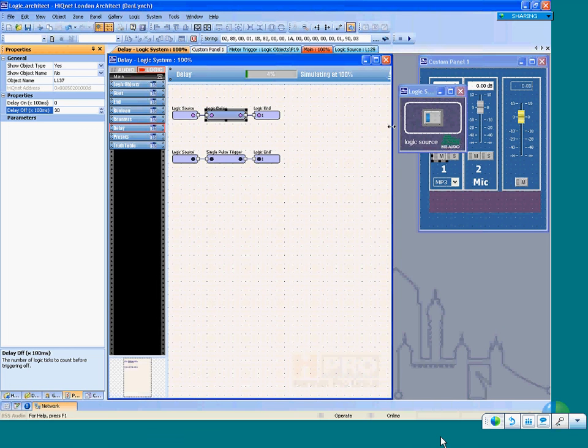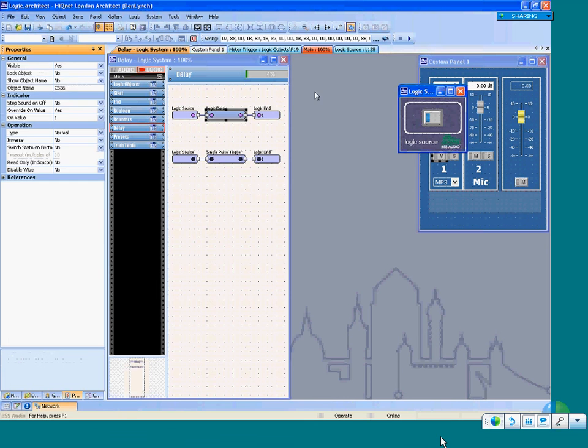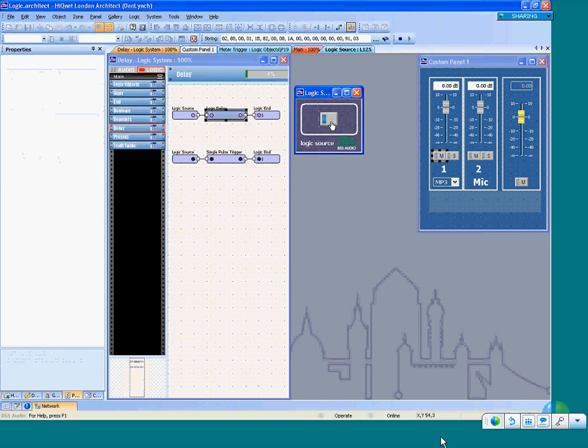And if you watch, here's how it's going to work. I'll bring this back over so you can see them a little more easily on the screen. When the fire system glitches and does a reboot, that's what we'll get, and the output is unchanged. So we don't even notice it. When the fire system goes into actual alarm state, 3 seconds later, we mute the audio, do whatever they're supposed to do. Just like we're supposed to do it.